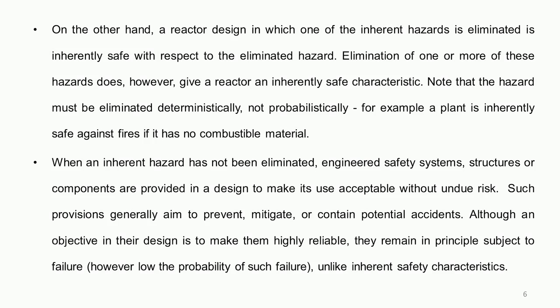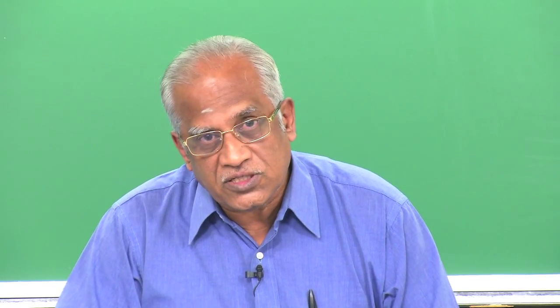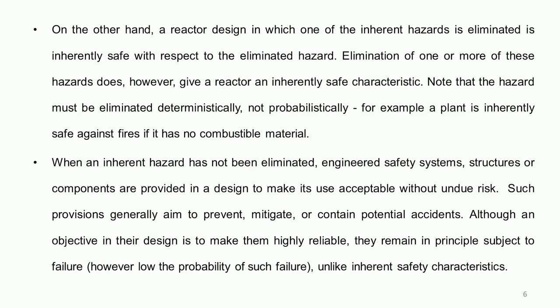When the inherent hazard has not been eliminated, we need to have an engineered safeguard system. For example, if there is fire, you see that the fire should not spread to nearby areas — you have fire-resistant structures so that fire in one area doesn't move to another. You need to provide structures or systems so that the risk is not undue. These provisions are essentially to prevent, and in case it happens, to mitigate and contain the consequences of accidents. Even though we make all the efforts in design, manufacture, construction, commissioning, and testing with good quality assurance to achieve a very minimum failure rate, in principle they are still subject to failures.